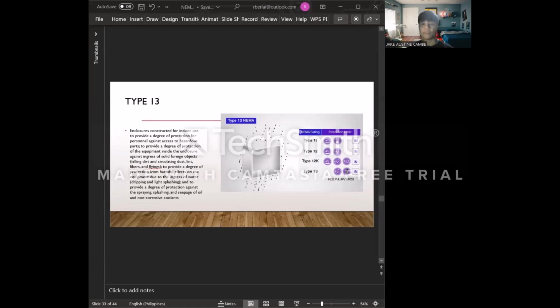Next is the type 13 NEMA enclosure. It is constructed for indoor use only to provide a degree of protection for personnel against access to hazardous parts. Next is to provide a degree of protection of the equipment inside the enclosure against ingress of solid foreign objects. For example, falling dirt and circulating dust, also lint, fibers, and even flyings. Next is to provide a degree of protection from harmful effects on the equipment due to the ingress of water, for example, in dripping and light splashing. And it also provides a degree of protection against the spraying, splashing, and seepage of oil and non-corrosive coolant.